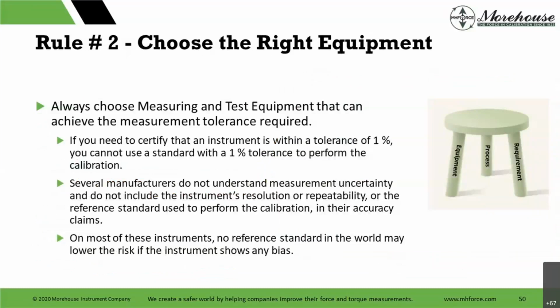Anyway, choose the right equipment. Always choose measuring and test equipment that can achieve the measurement tolerance required. If you need to certify that an instrument is within a tolerance of 1%, you really can't say, oh, I'll just buy a standard that's 1%. We see a lot of people do that, right? Oh, a 1-to-1, that's good enough. Again, back to that risk formula when you put the reference standard in it.